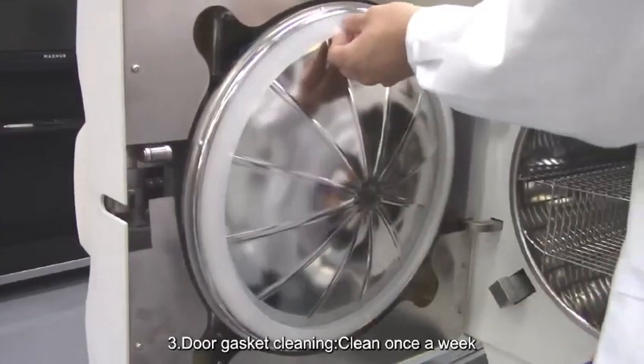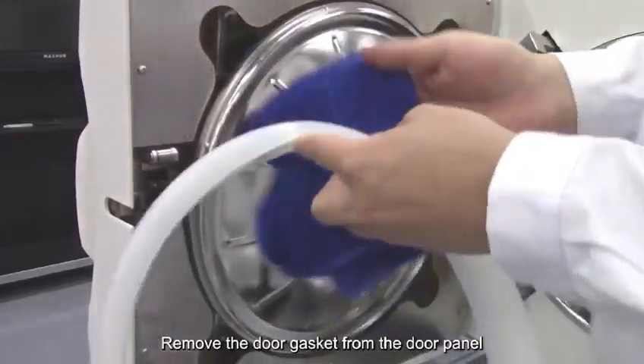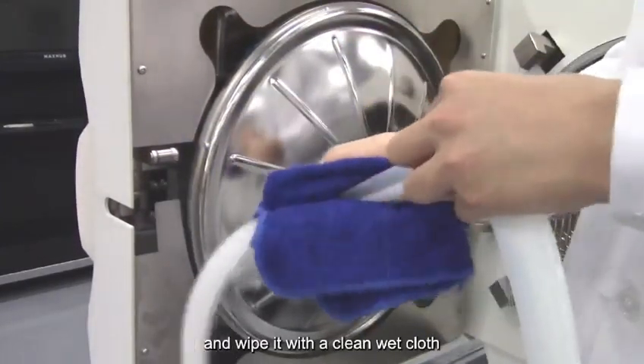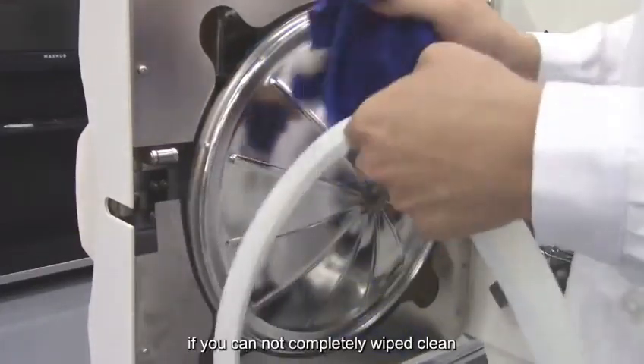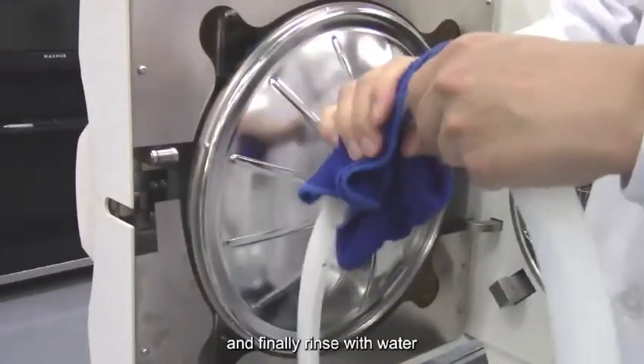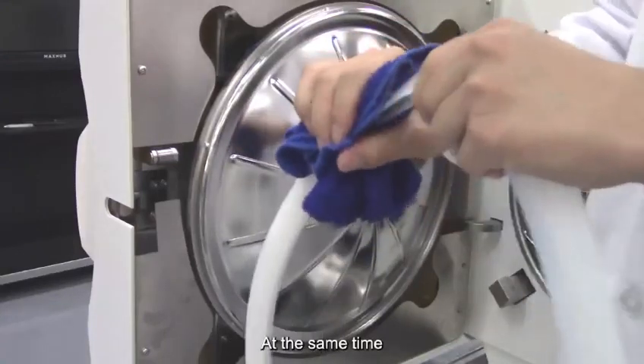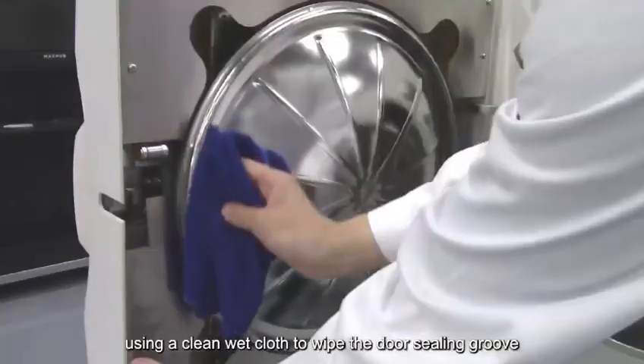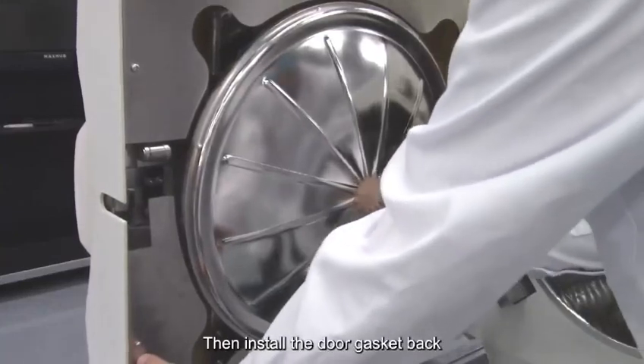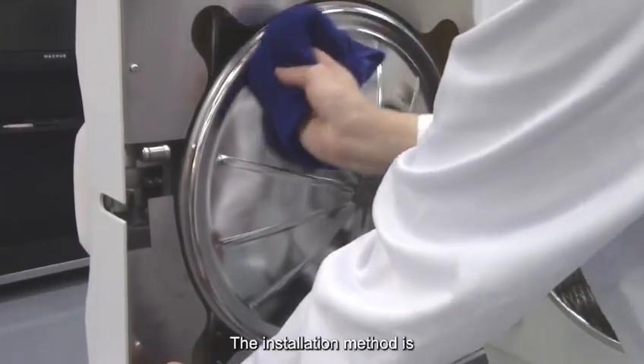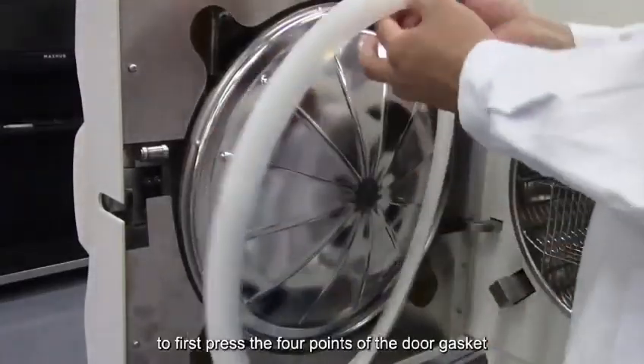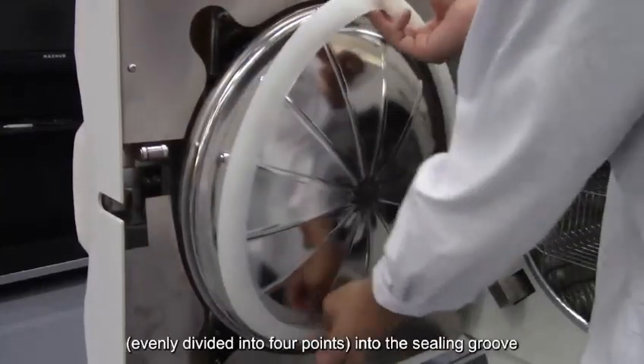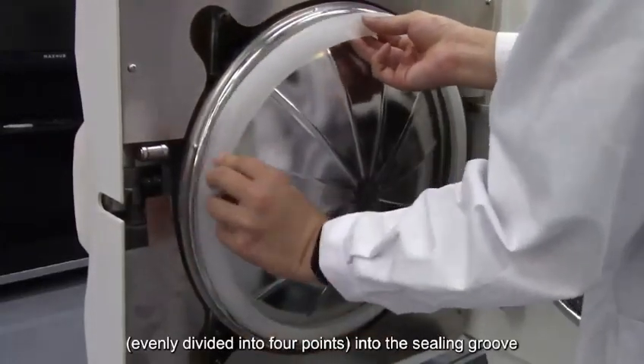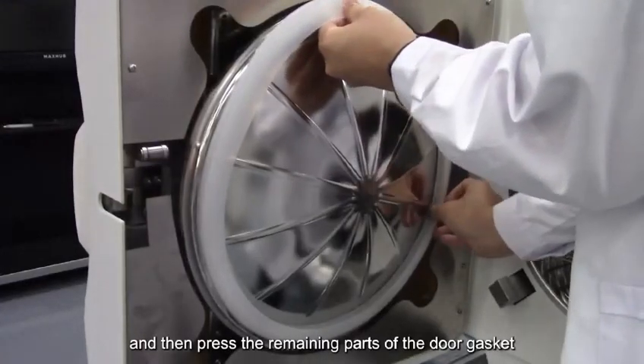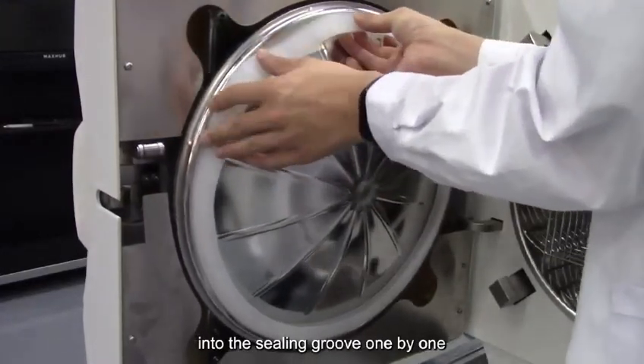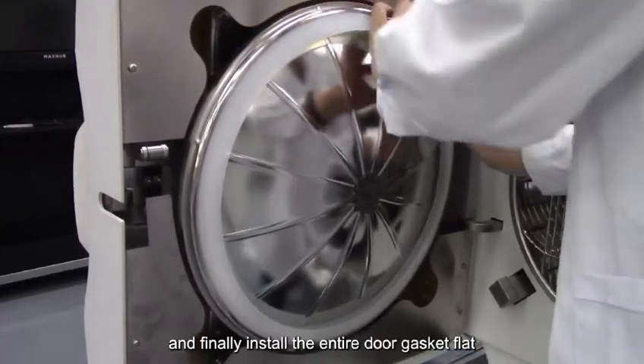3. Door gasket cleaning. Once a week, remove the door gasket from the door panel and wipe it with a clean wet cloth. If you cannot completely wipe it clean, you can use neutral detergent, and finally rinse with water. At the same time, use a clean wet cloth to wipe the door sealing groove. Then, install the door gasket back. The installation method is to first press 4 points of the door gasket, evenly divided, into the sealing groove, and then press the remaining parts of the door gasket into the sealing groove one by one, and finally install the entire door gasket flat.